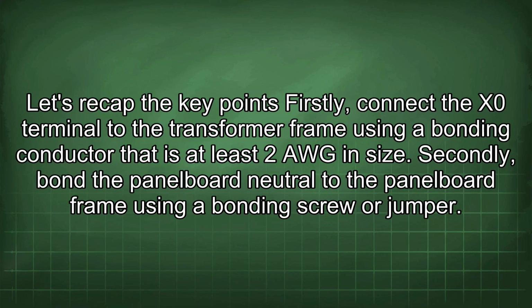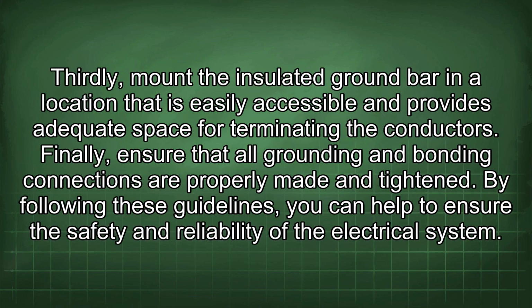Let's recap the key points. Firstly, connect the X0 terminal to the transformer frame using a bonding conductor that is at least 2 AWG in size. Secondly, bond the panel board neutral to the panel board frame using a bonding screw or jumper. Thirdly, mount the insulated ground bar in a location that is easily accessible and provides adequate space for terminating the conductors. Finally, ensure that all grounding and bonding connections are properly made and tightened. By following these guidelines, you can help to ensure the safety and reliability of the electrical system.